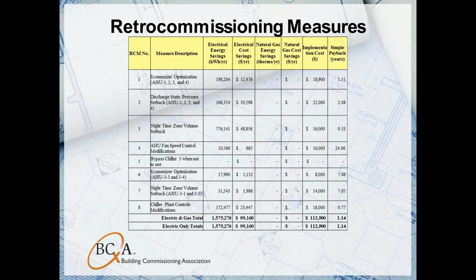Many of the tenant spaces are only occupied between 6 a.m. and 8 p.m., so we recommended a nighttime setback at the VAV box level. Airflow set points and temperature set points were modified for unoccupied mode. Important for this building, there are some cooling-only boxes, so we're okay to set the minimum airflow set points on those in unoccupied mode to 0 CFM.